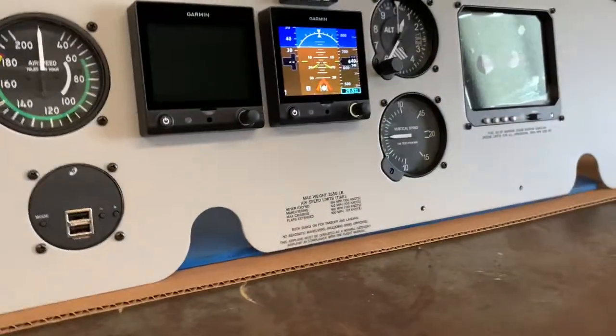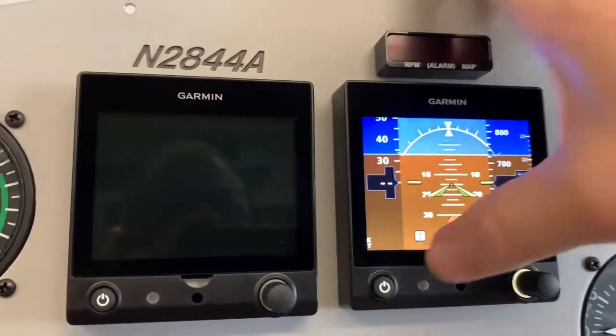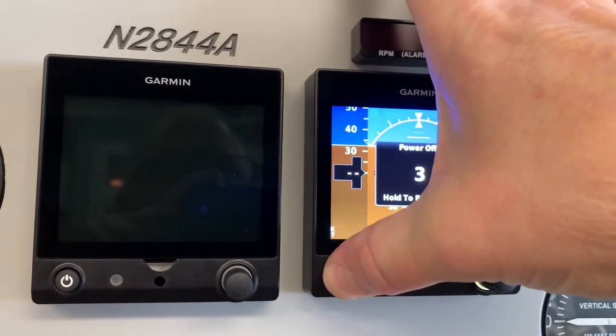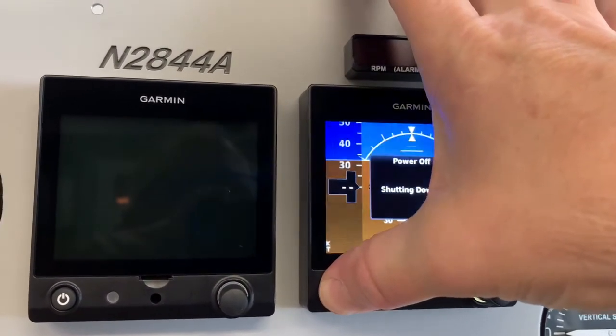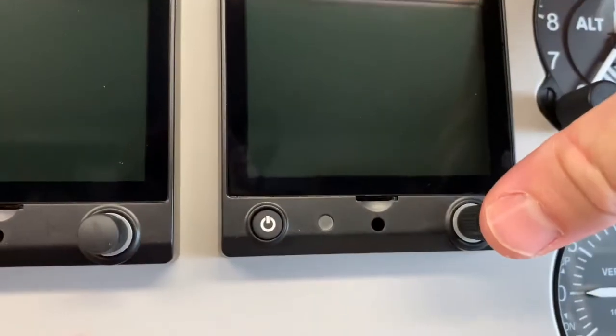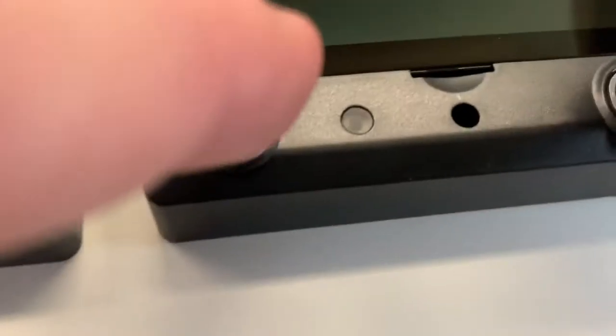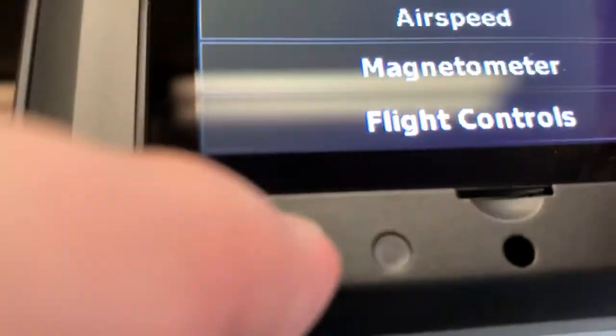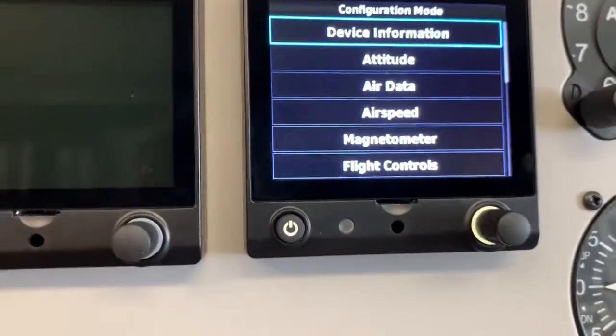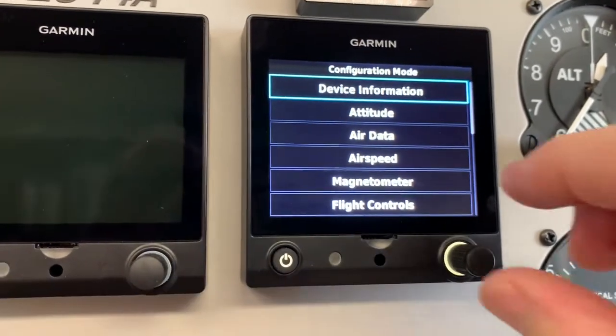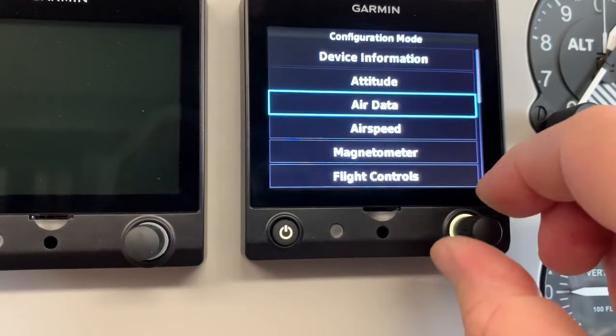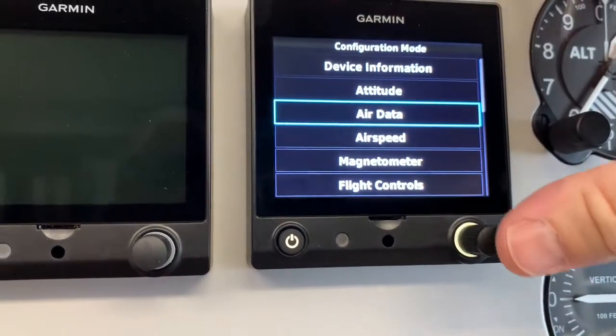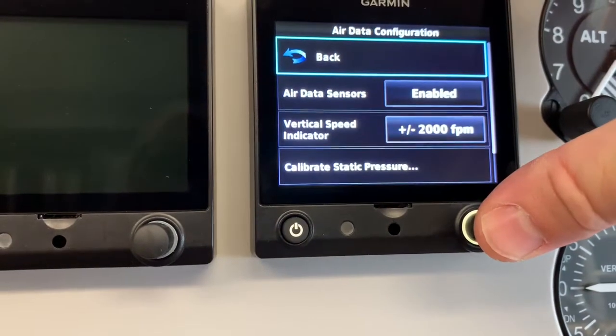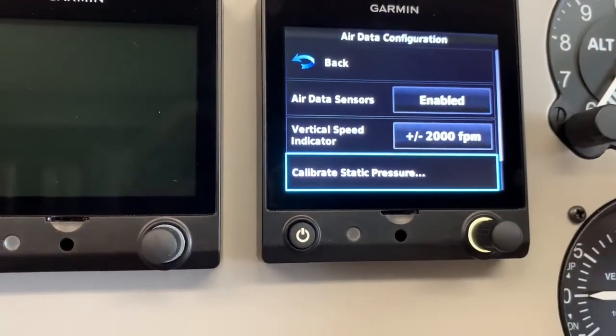So the first thing is to calibrate the G5. To do that, you need to go to the maintenance mode. So we'll turn off the G5, and then we will hold in on the knob. We'll simultaneously, this is hard to do holding a phone, push the power button. And there you go. It powers up into the configuration mode. And here you can set various device information, but we want to go down to the air data and calibrate static pressures.